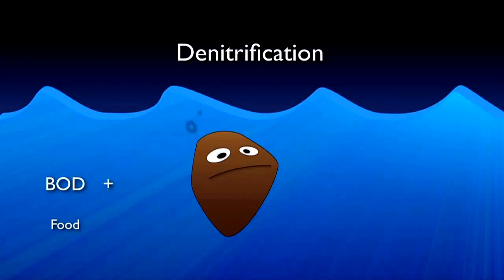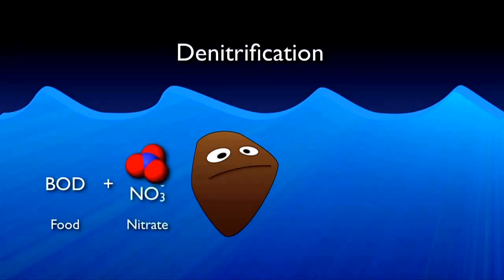If there is no dissolved oxygen present, however, the denitrifying bacteria look to alternative sources such as nitrate. These specialists have the ability to strip the oxygen from nitrate molecules to satisfy their needs. This critical environment — where no DO is present yet nitrates are — is referred to as anoxic, and is absolutely required for denitrification.